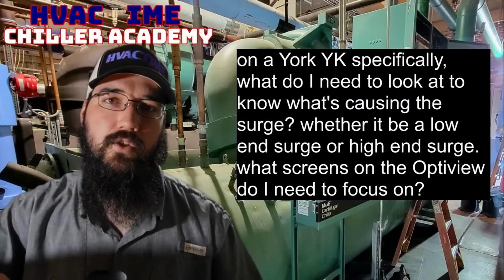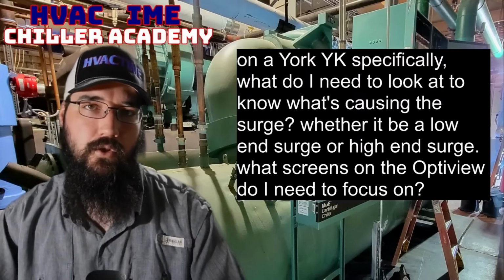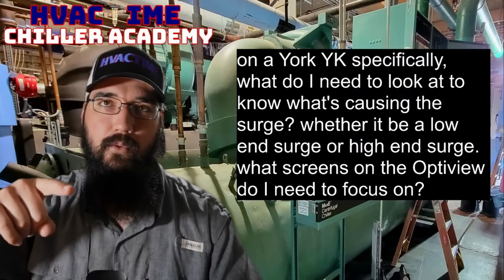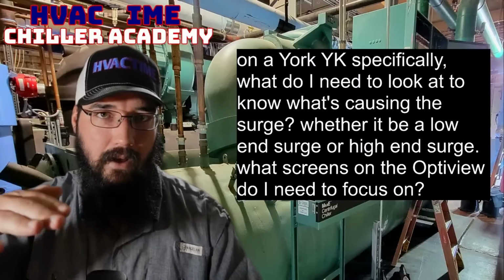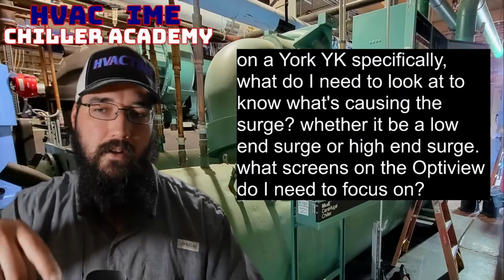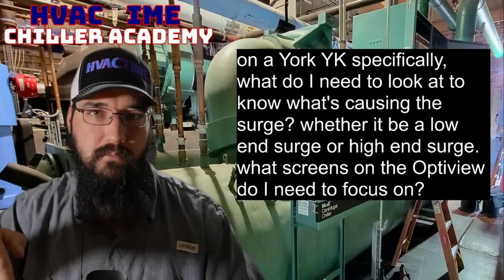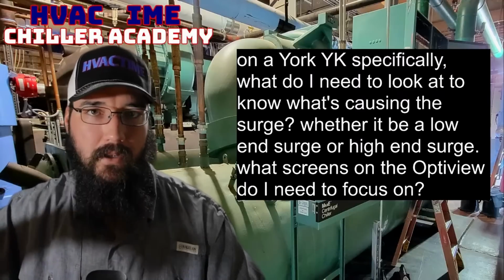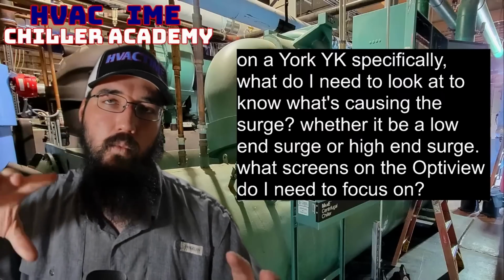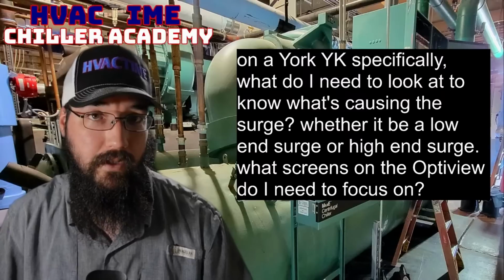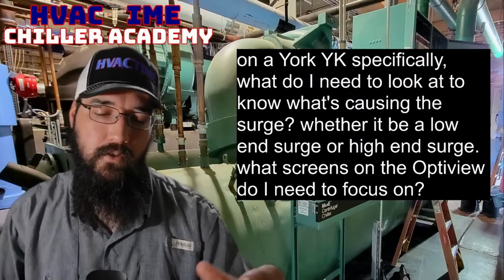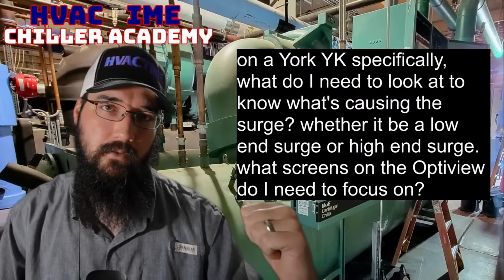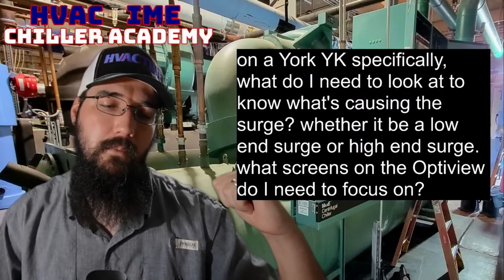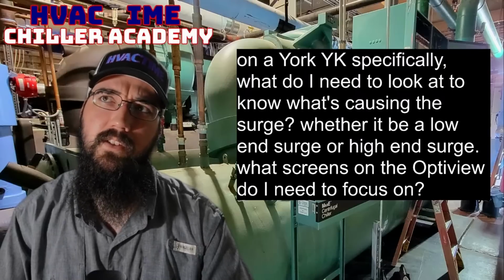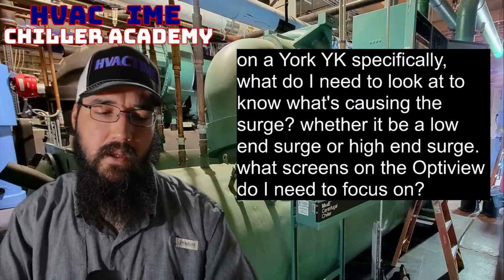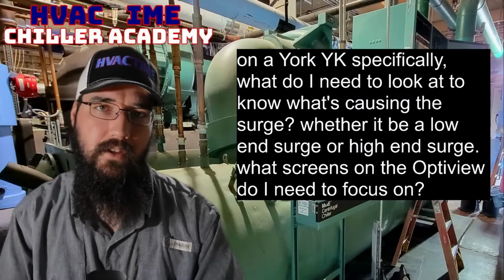And essentially, when you start to enter into a stall and then surge state, that reading will become more erratic. It won't have quite as much stability in its feedback. It'll have a lot of, say, dips, if you will, and spikes. So it'll become erratic. The worse the condition gets, the more erratic that sensor will read. Then the stall detection module outputs a voltage signal to the main board or the ACC board, and it uses that voltage as a detection threshold.